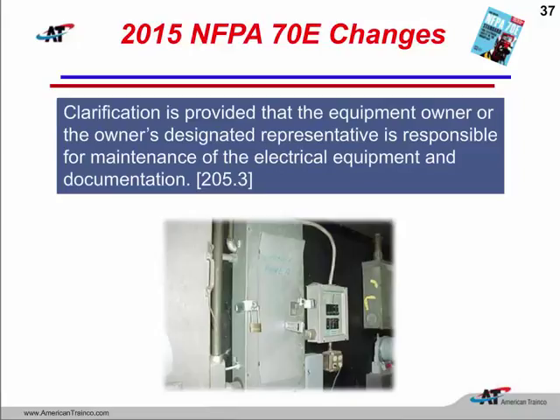That label is now a label that 70B would like to see on that piece of equipment to give that qualified worker an idea: can I operate this equipment really normally? I can come up and operate it, turn it on or off with no PPE because it was installed properly, it was maintained over the years. Or if it hasn't been maintained, hey, I'm going to have to go and get some PPE on to protect myself because who knows what's going to happen when I turn this on or off. So the maintenance of the electrical equipment has been stressed very heavily in this edition of 70E.